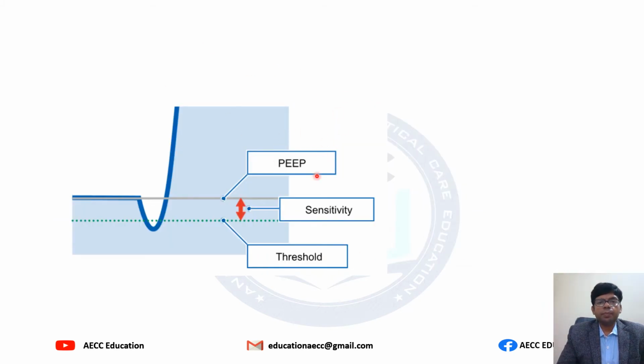To utilize the patient triggering, you must activate the pressure triggering and set the pressure trigger sensitivity. The sensitivity is a negative value in centimeter of water.